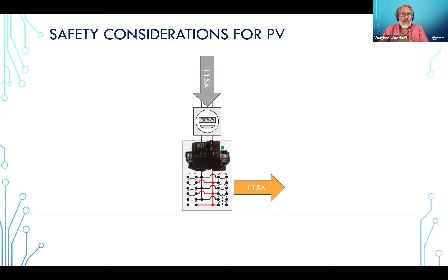I have a main breaker in my service panel, right? That's going to open up to disconnect the power so that the service panel is not damaged, that any of the downstream stuff's not damaged, and even the wiring from this panel to the utility is not damaged.